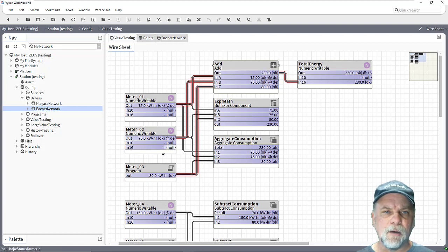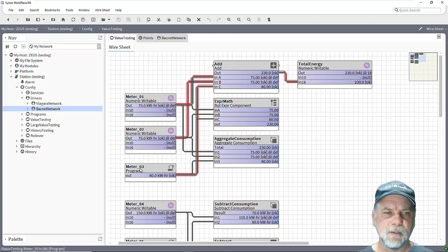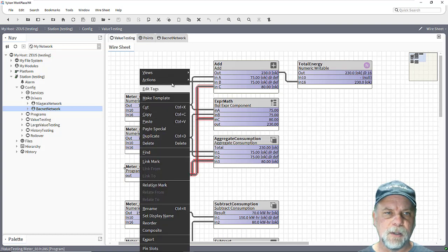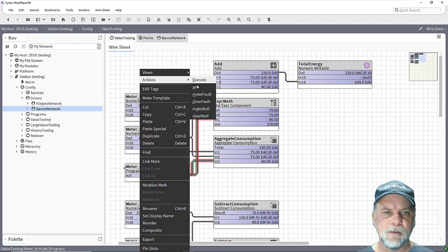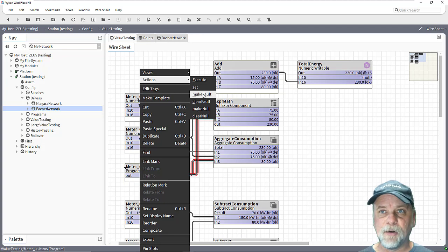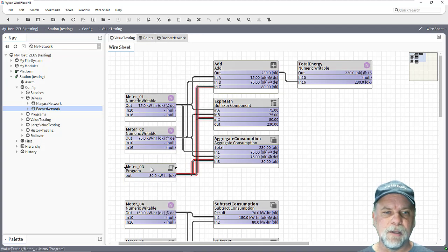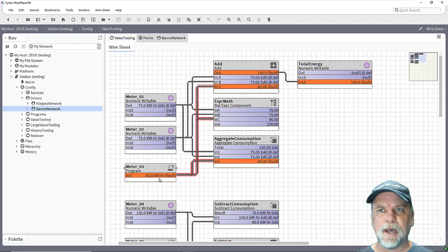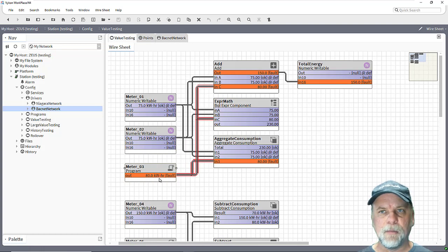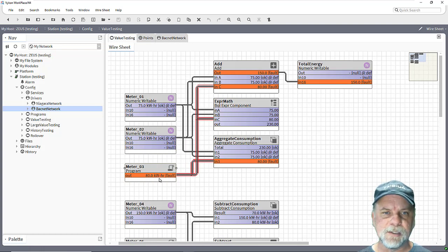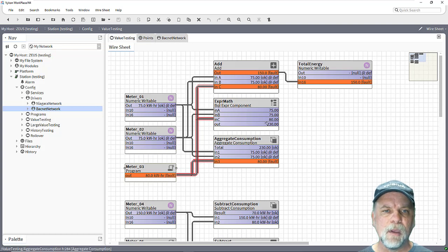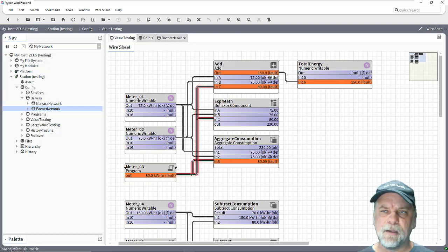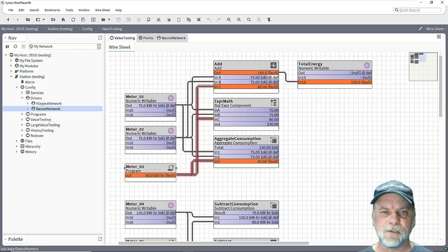So we can see that currently the three numbers being added together sum up to 230. Now let me introduce a fault here and for the first fault I'm just going to cause it to have a fault status actually on the output here. So we're still reading a value but it has a fault status, something maybe with the driver had a polling exception or something of that nature.